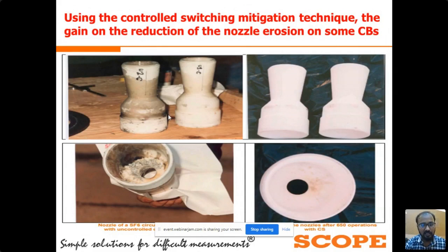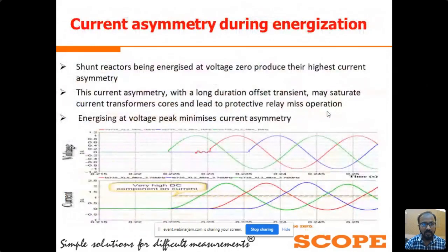Here we can see the image on the left side. This is the nozzle of the circuit breaker without using any control switching device, and on the right side you can see the nozzle system of the CB contacts with the same operation by using the control switching device. So by using the control switching device for the de-energization of the shunt reactor, we are minimizing the effect of reignition of current between the CB contacts.